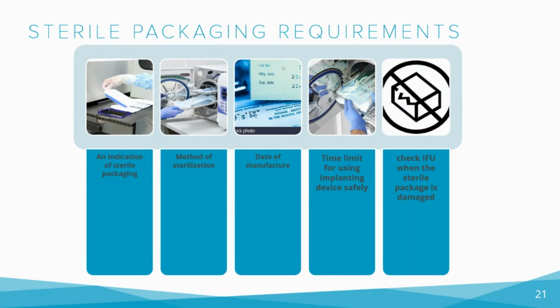In addition to the specific indication, the EU MDR also requests that the sterile packaging be designed, manufactured, and tested to maintain the sterility of the device until the packaging is opened or the device is used. It is important for healthcare providers and patients to follow the specified indication for sterile packaging to ensure the safety and effectiveness of the medical device.